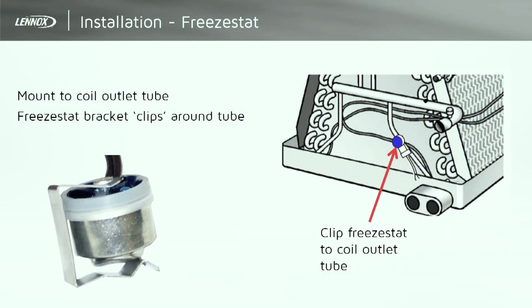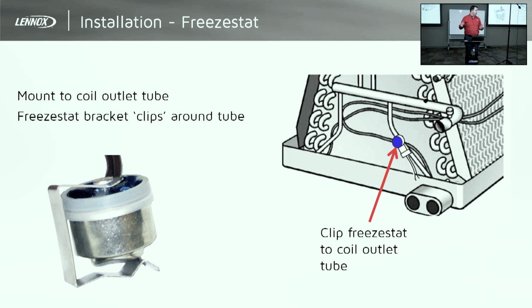Now, to your point, the discharge air temperature sensor will be used as a quote unquote freezestat or a high limit trip. So it's going to monitor that discharge air temp. And sometimes that happens if you're using this with a single stage system or even a 2-stage system and we're just not moving enough airflow, we're trying to do a 200-300 CFM zone, either in heating or cooling. Your discharge air temp gets too low in cooling, and in heating the discharge air temp gets too high, and it will see that and go, all right, I'm shutting you off.